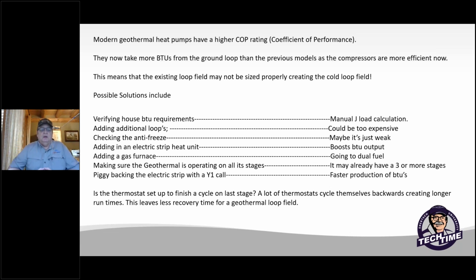You can always add a gas furnace alongside the heat pump. Some special ductwork you do helps make it going into a dual fuel, and some electrical cooperatives areas have dual fuel electric rates, so you can get by with cheaper electricity running the heat pump. They require backdraft dampers if you put one alongside of it, or you can always make sure and do a new furnace and do a geothermal split system and do a real simple, easy conversion in that aspect.